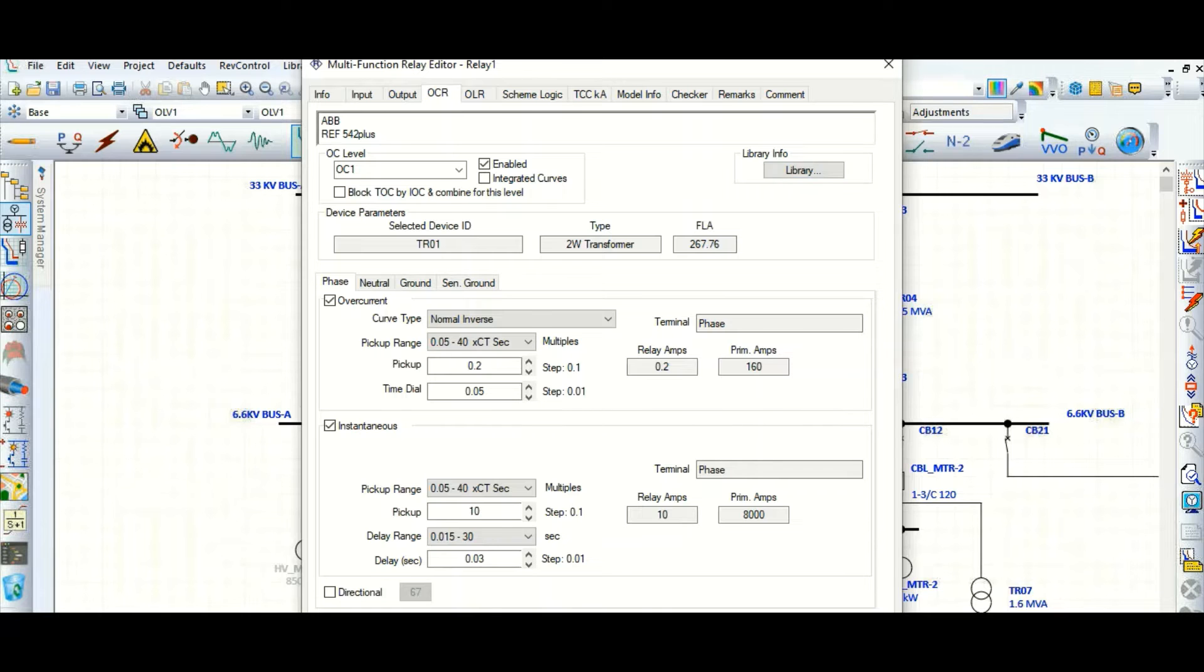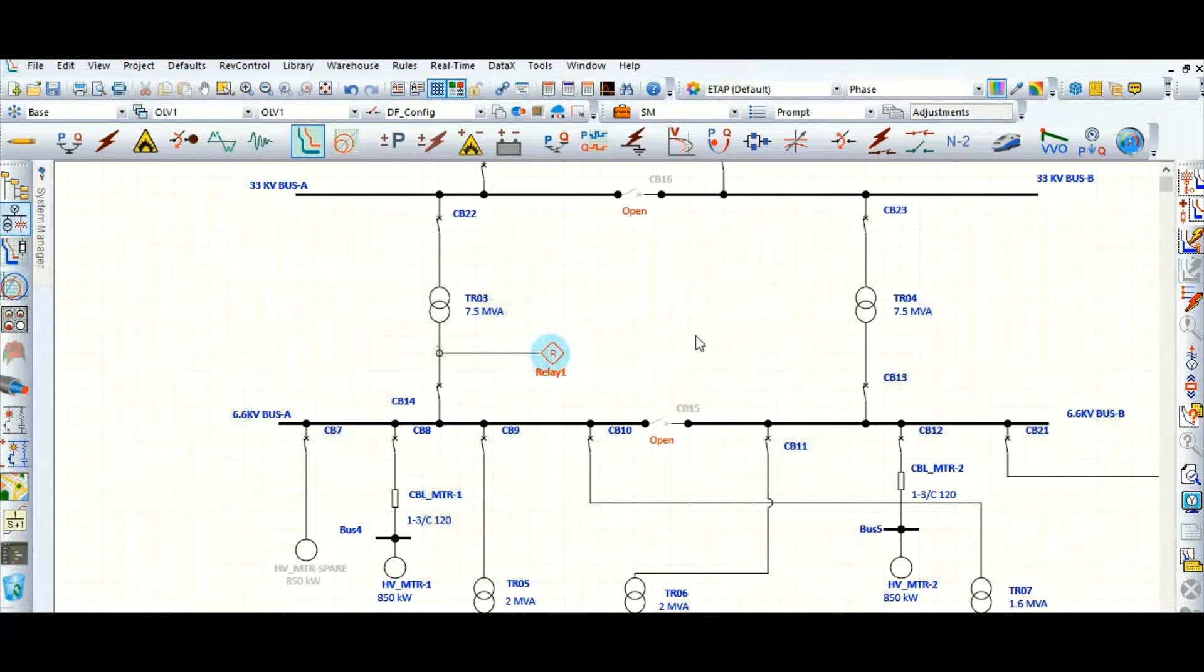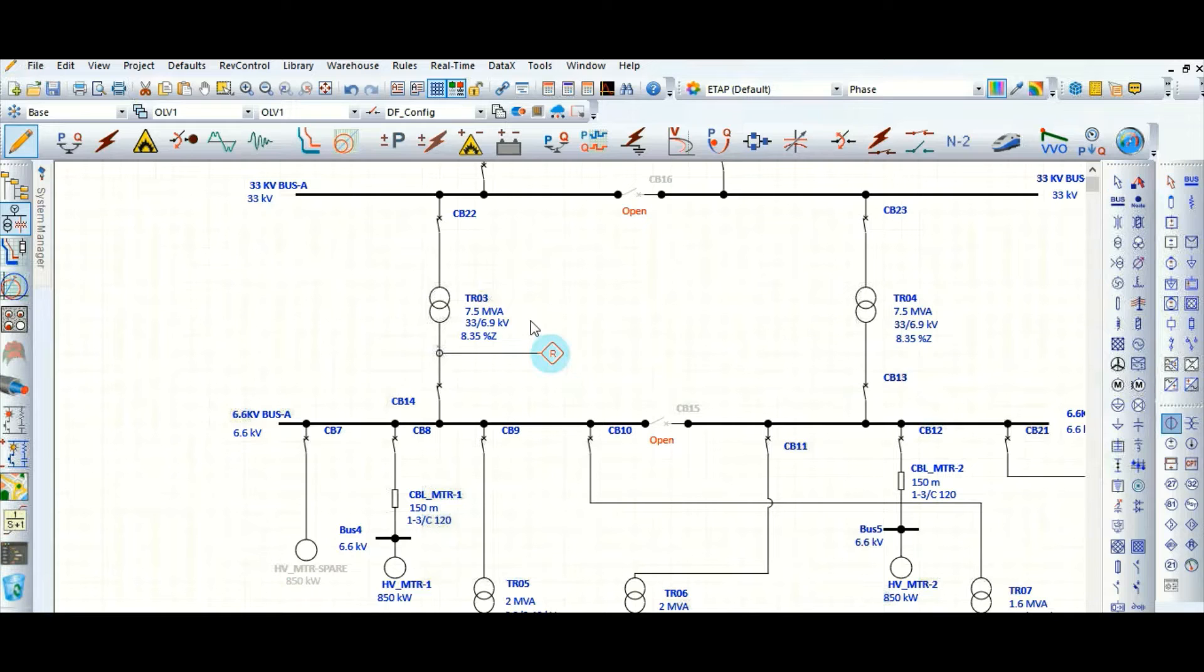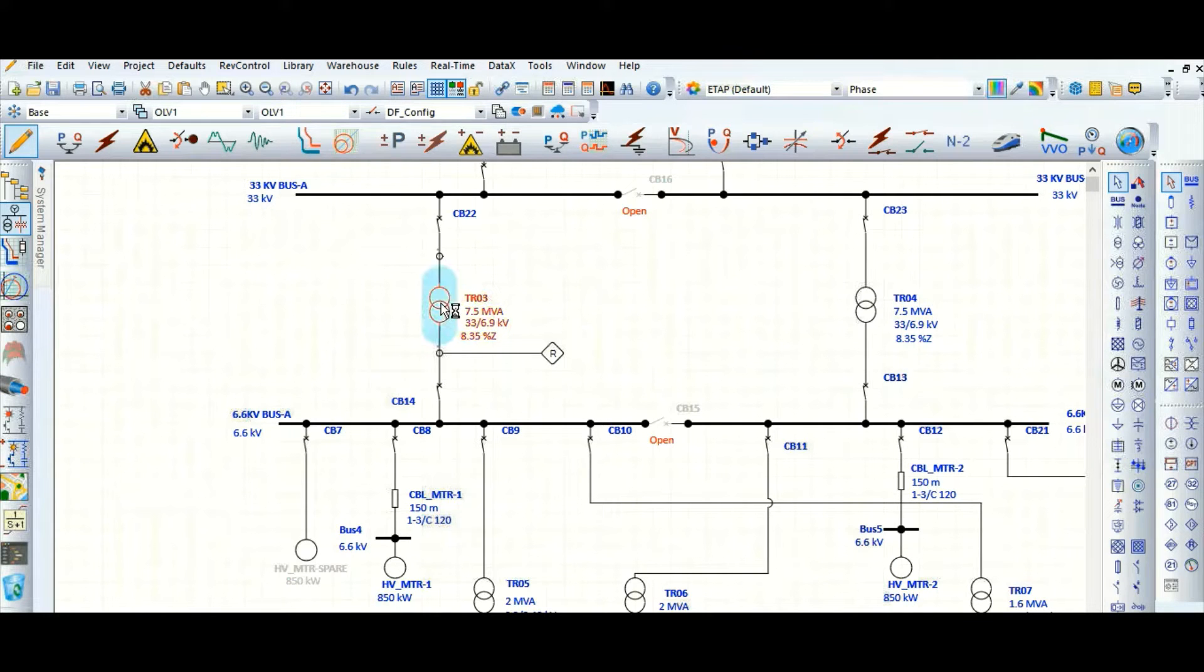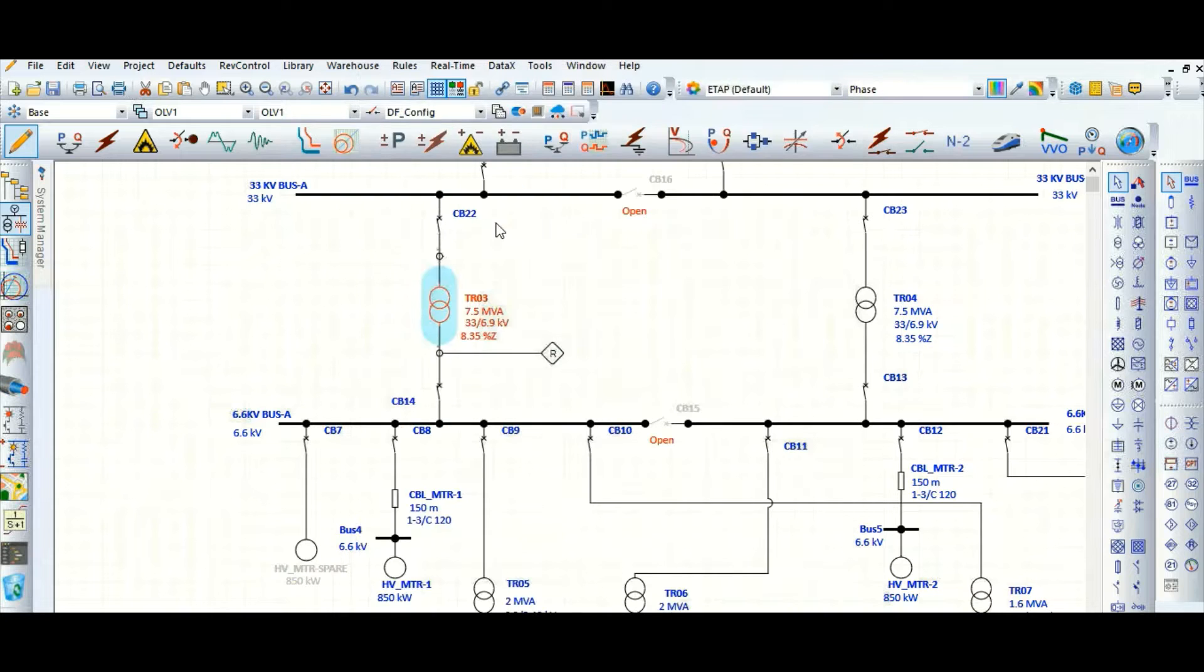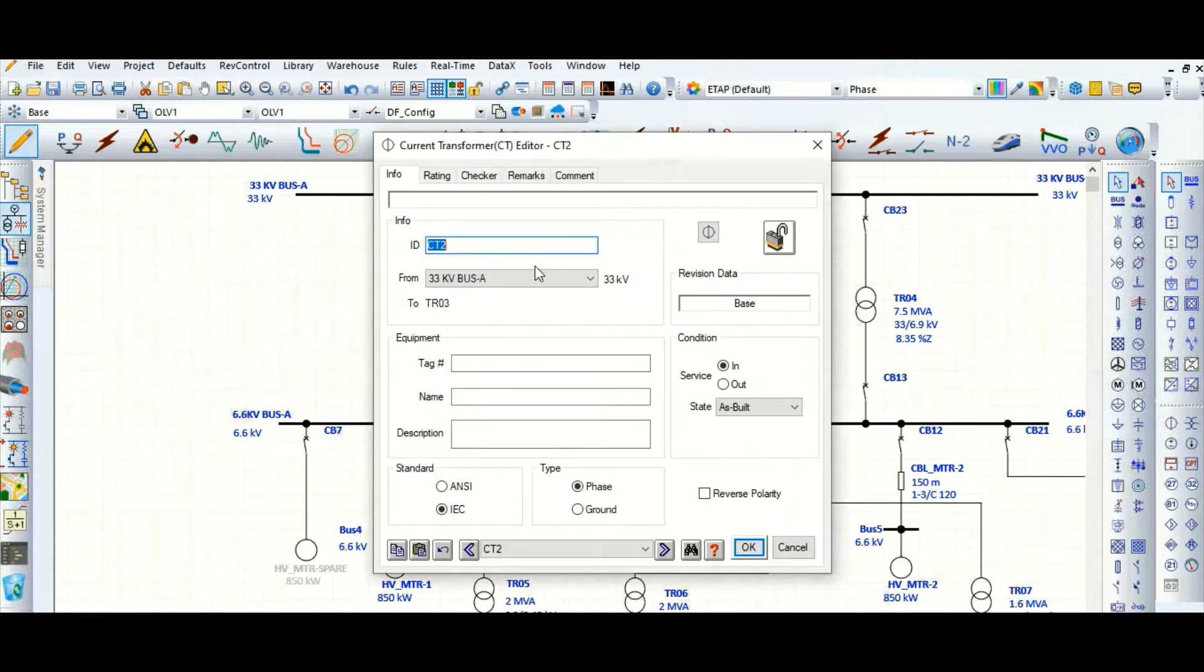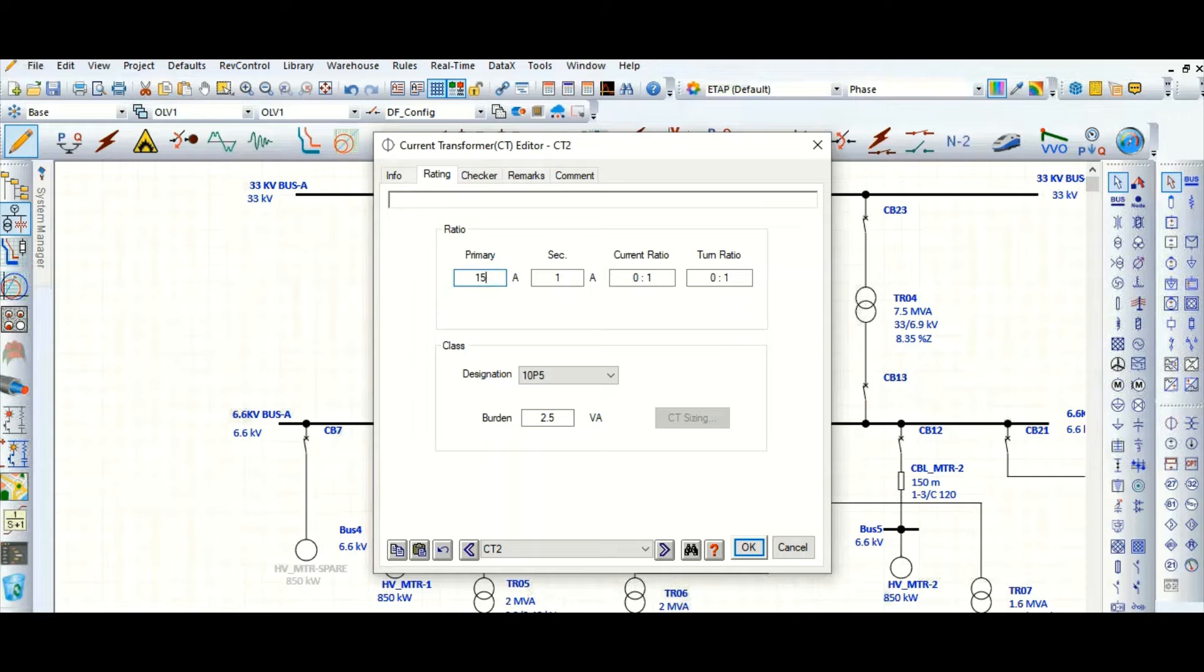Let's assign in the transformer high voltage side one CT. Go to edit mode and select one CT. What will be the CT rating? Let's check the transformer HV side current rating which is 131.2 ampere. So let's select this CT ratio as 150 bar 1.